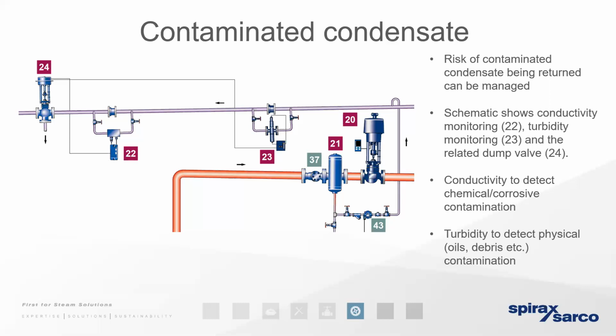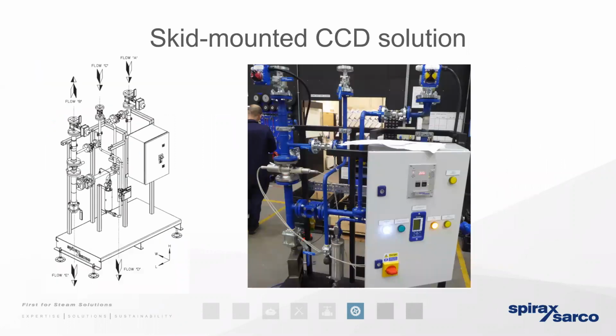So we've spoken previously about how we can detect contaminated condensate, and we can do that by using either a turbidity probe or a conductivity probe. So that will identify very, very quickly when there's a problem with the condensate. So if there's a risk of contamination, the probe will send a signal to a diverting valve and it can be dumped. So it means for the majority of the time, we can recover the condensate and enjoy those cost savings. And contamination control devices can either be mounted in line, or for larger solutions, they can be skid mounted.